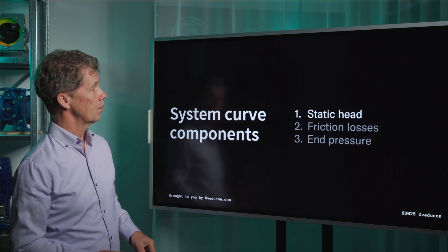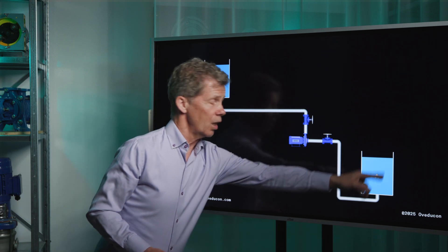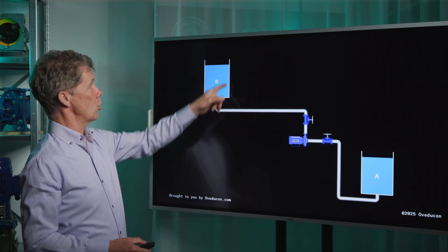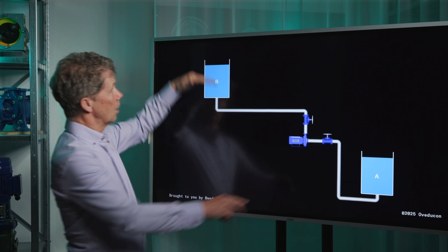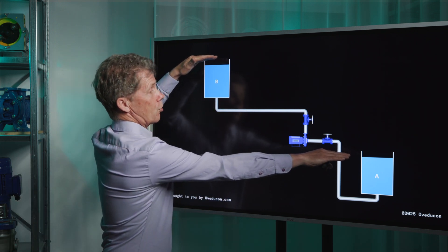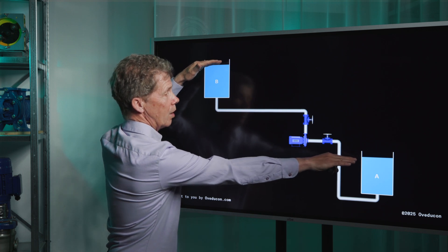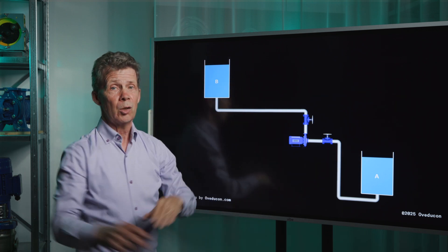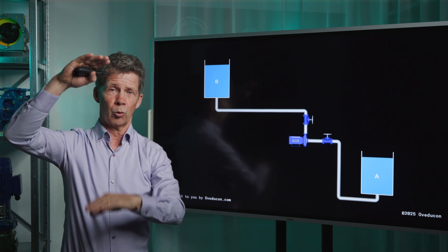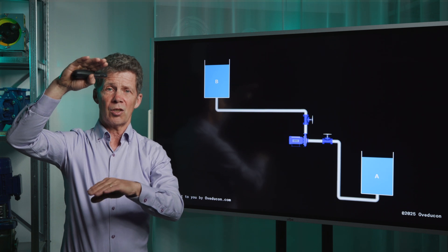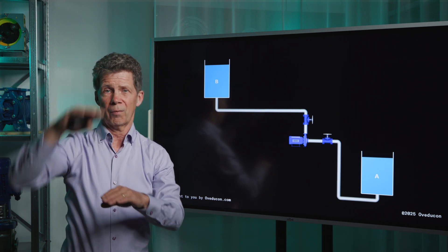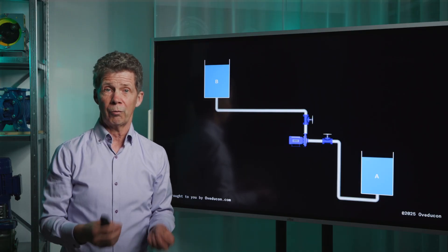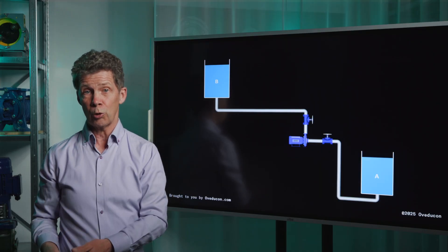Let's start with your static head. We have a suction tank A here and a discharge tank B here. The medium level differs — we have to move the medium from tank A to tank B, and you have to overcome a certain vertical distance or length. This distance or length is called your static head. If you want to know how to determine your static head in a number of different situations, we made a special video about it and you can find it on our YouTube channel. We put a link to this video below.